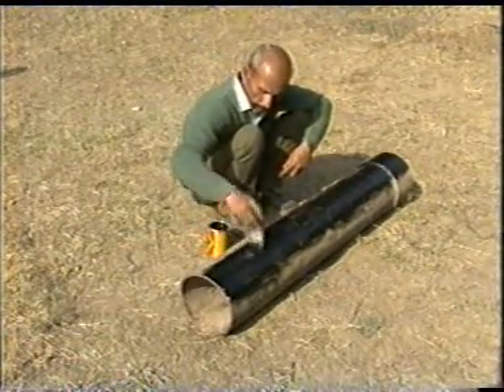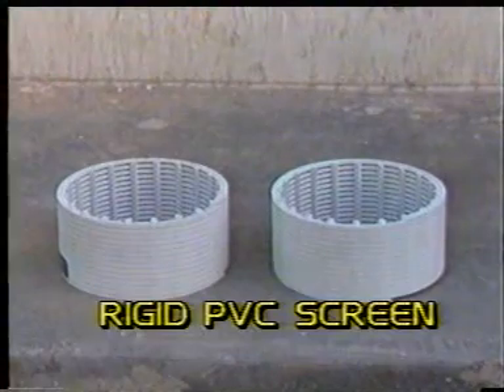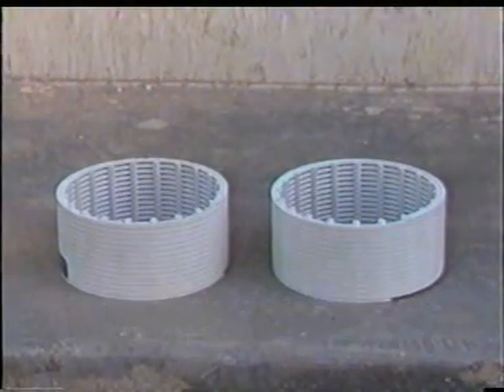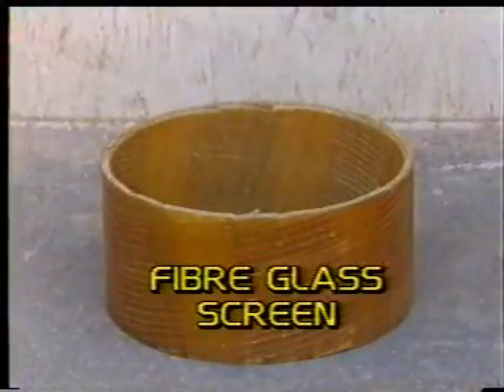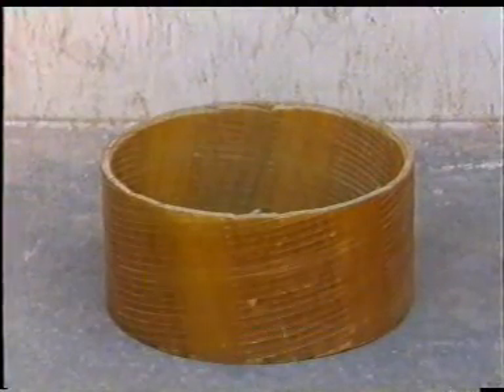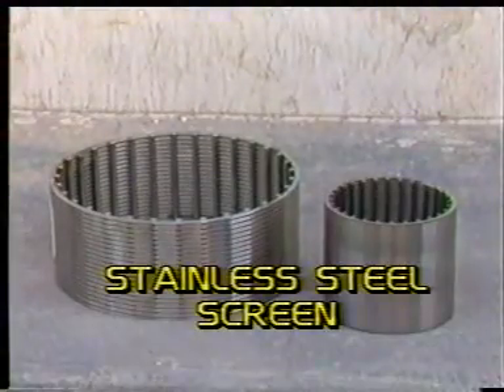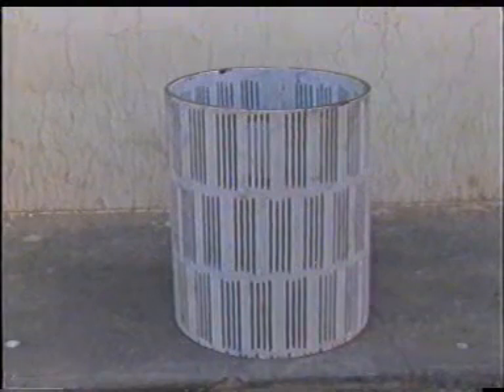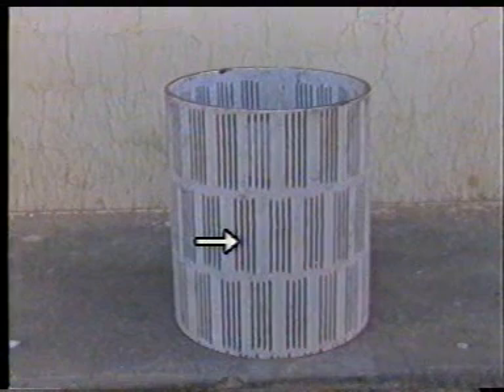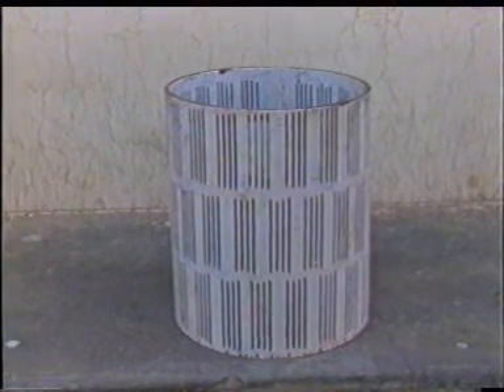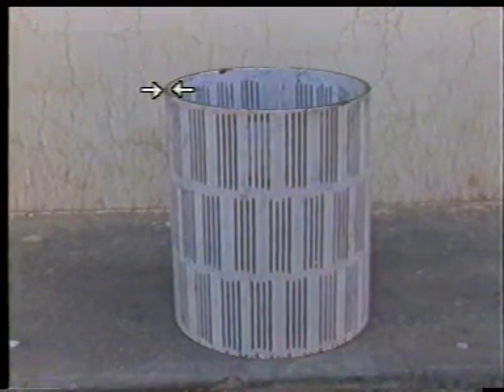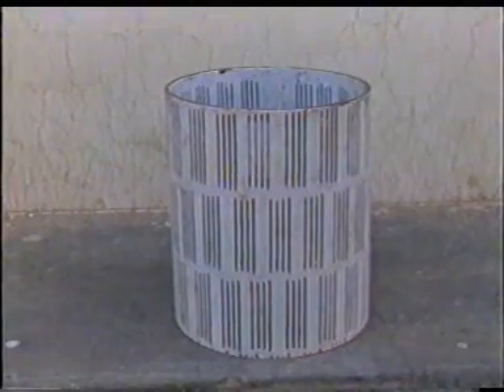Alternatively, corrosion resistant pipes such as rigid PVC pipes, fiberglass and stainless steel etc. could be used. Under corrosive conditions, well screens should be preferred with large open areas and comparatively thicker pipes coupled with low rate of pumping.